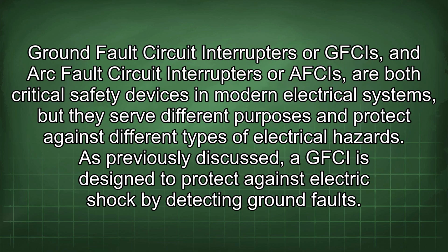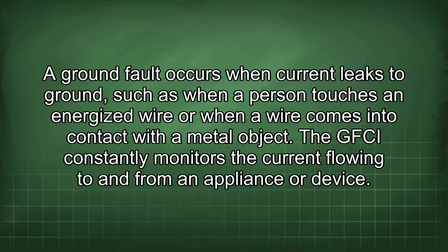Ground fault circuit interrupters, or GFCIs, and arc fault circuit interrupters, or AFCIs, are both critical safety devices in modern electrical systems, but they serve different purposes and protect against different types of electrical hazards. As previously discussed, a GFCI is designed to protect against electric shock by detecting ground faults. A ground fault occurs when current leaks to ground, such as when a person touches an energized wire or when a wire comes into contact with a metal object.